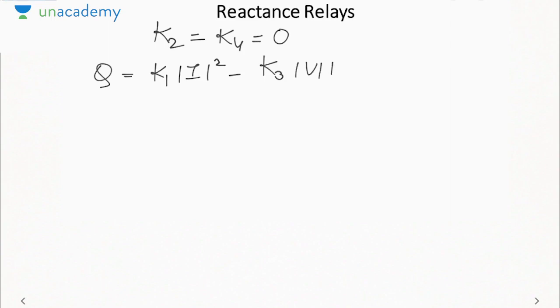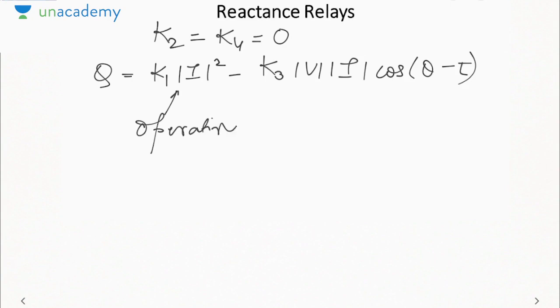Next is your reactance relay. Now here we will consider the directional element. So here we equate K2 and K4 to 0. So torque will be K1 mod I square minus K3 mod V mod I cos of theta minus tau. Now here this will be called as operating torque and this will be my restraining torque. Okay.